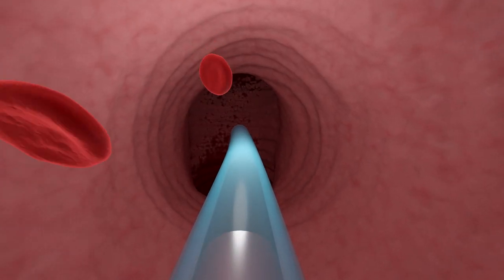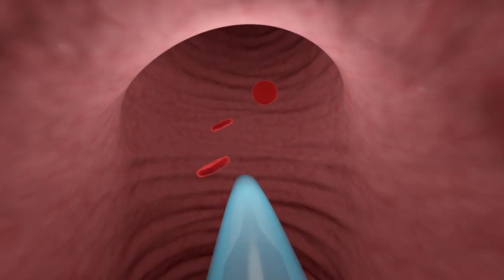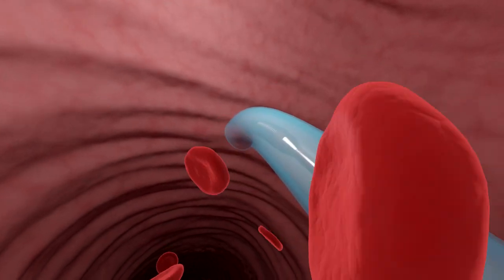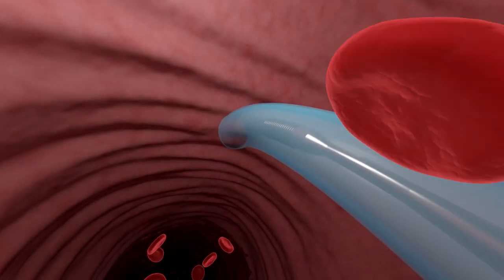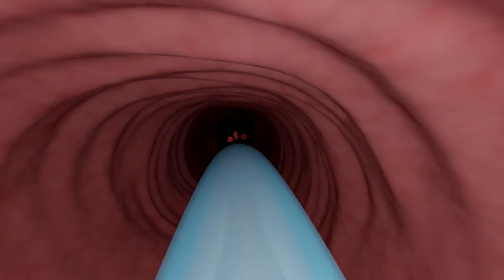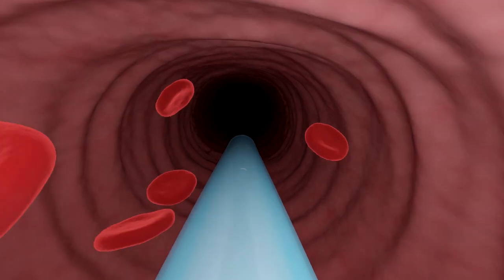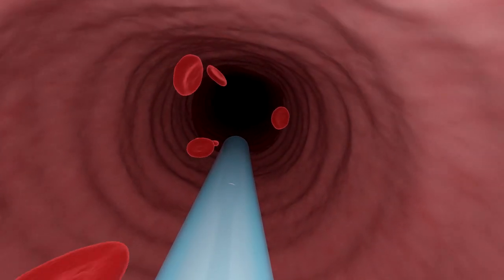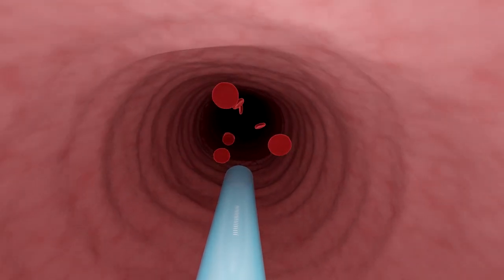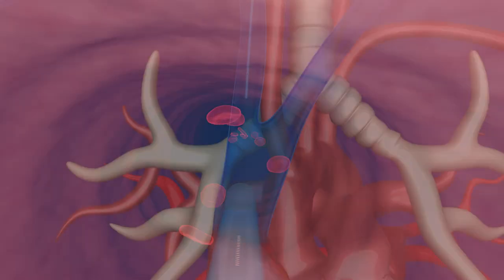Once the PICC tip reaches the wall of the brachiocephalic, the slight angle built into the stylet near the tip helps point the catheter toward the SVC. Then the short floppy section of the stylet allows the PICC to deflect off of the brachiocephalic and slip downward into the SVC. The NaviCurve Stylet is designed to make it easy to advance the catheter into the SVC on the first attempt without the need for withdrawal and reinsertion of the catheter.